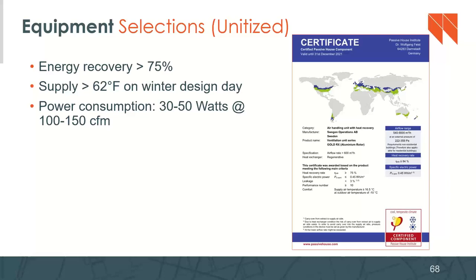You want to look at how cold it could possibly get where I'm installing this thing, and am I going to be able to maintain a fresh air supply into the building, into your apartment or house, of greater than 62 degrees on the coldest winter day that you are expecting to get? If the answer is no, then you might need to look at a duct heater. That would be a supplementary piece of equipment that usually sits between the outside air intake and the ventilator itself to bring the temperature of the air up on these very cold days, very cold nights.